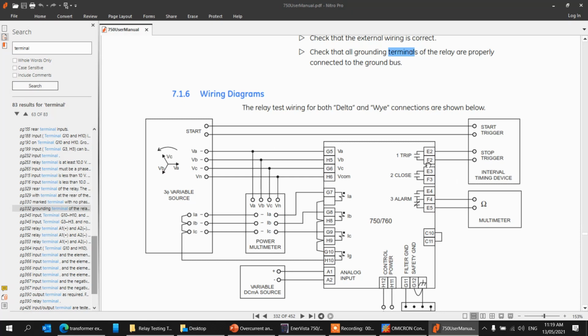If you remove this one, you open the loop and break the circuit. So to make it safe, especially on 369 relay, to save time, just remove one leg instead of removing both. Let's say in this case remove F2, connect your leads there, and the other lead should be on the E2.